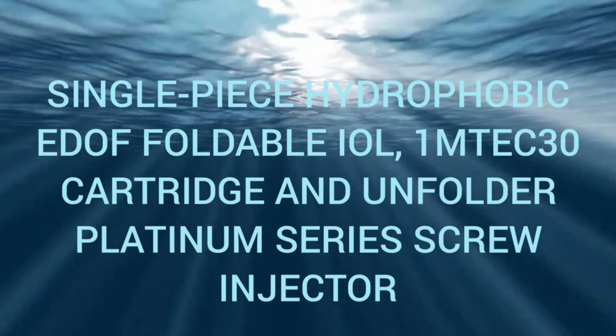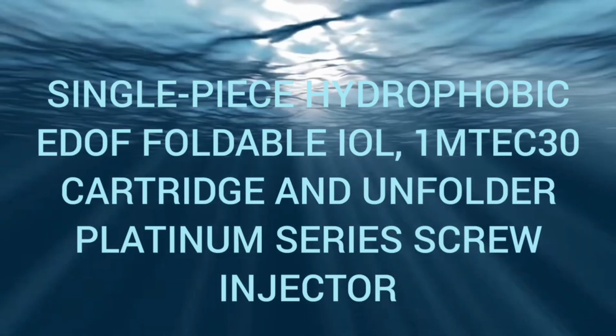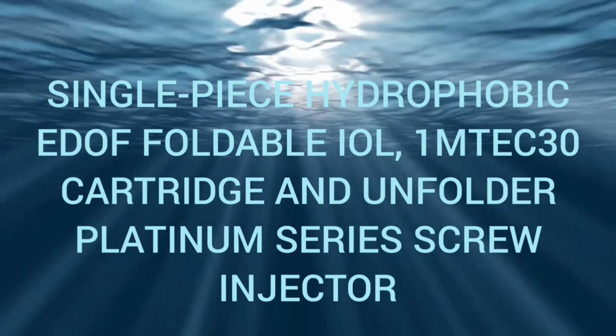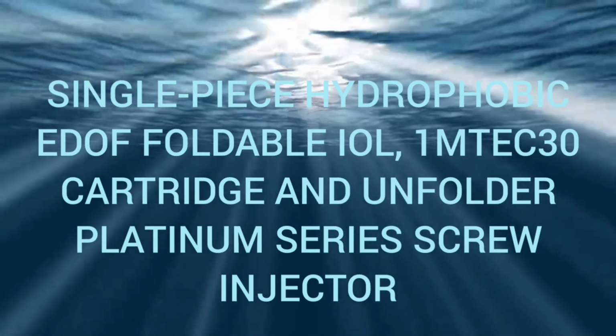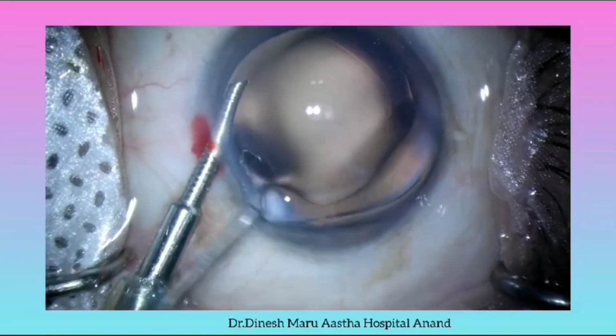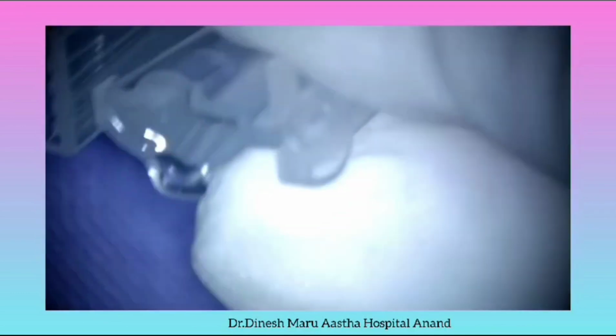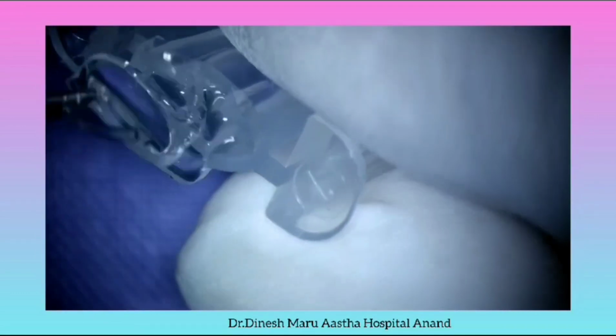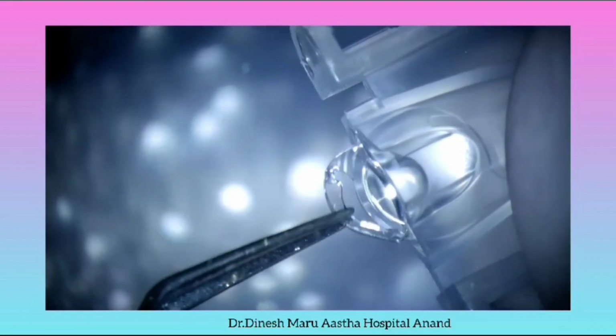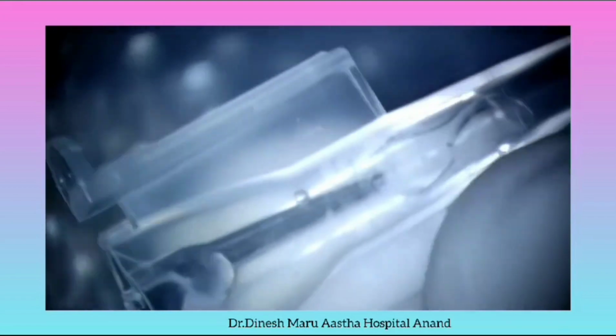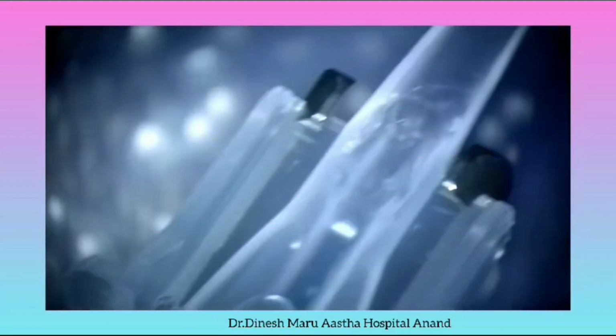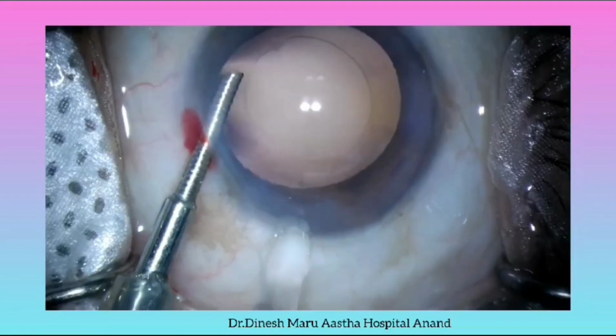Single piece hydrophobic EDOF IOL, 1 MTEC 30 cartridge and unfolder platinum series screw injector. Ensure the corneal incision matches the 2.2 to 2.4 mm lumen size of the cartridge for seamless insertion. Load the IOL into the rear loading cartridge as shown, securing it firmly into the groove of the screw injector. Push the plunger to carefully position the lens and eliminate any surplus viscoelastic material.